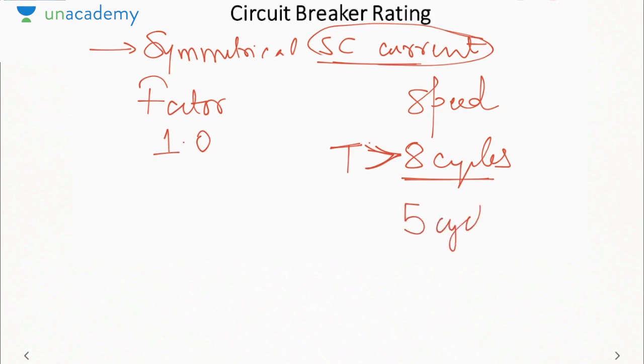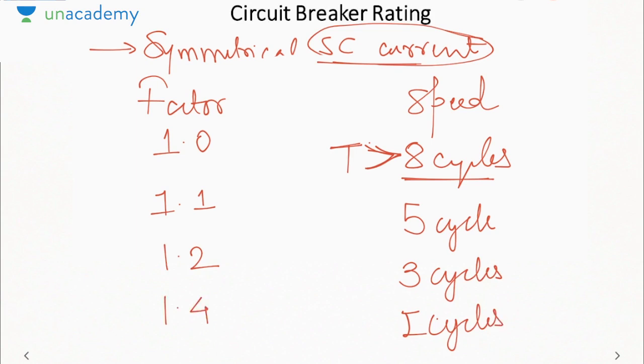Now if we are taking a 5 cycle circuit breaker, that is, it opens in 5 cycles, then we will multiply it by 1.1. Then for 3 cycles, we will multiply it by a factor of 1.2. Then for 2 cycles, 1.4. We do not go beyond 2 cycles. Why? Because beyond 2 cycles we will enter the subtransient region, and we always open the circuit breaker in the transient region. We never open the circuit breaker in subtransient because the current is very high, due to which the arc formed will be very dangerous and hard to extinguish. So we will open only in the transient region.